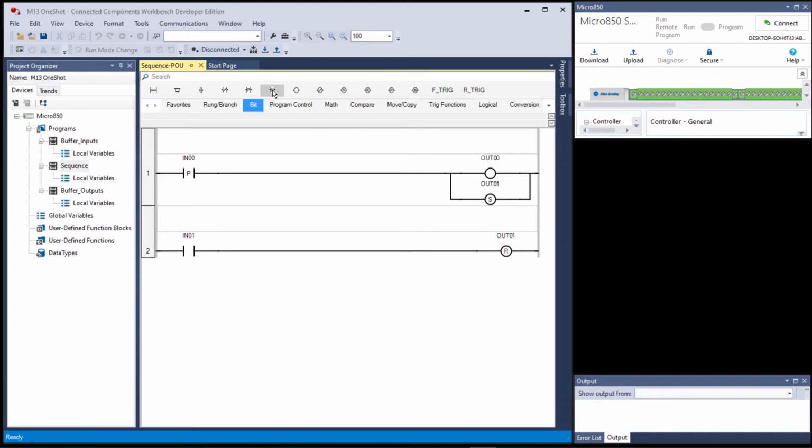And I'm talking about a button now, so I'm actually looking at an I/O point. This could be any bit in memory, it doesn't matter what it is. This instruction has no idea where that bit is or where it came from. Now, in your data table, IN00 knows where that bit's at because it points to it. It's an actual I/O which gets its state determined by the screw terminal when you're in run mode.